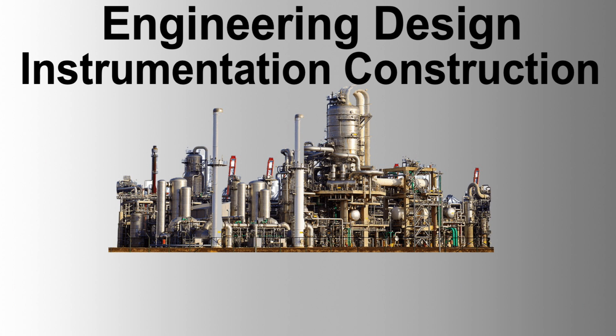Grounding and shielding. Instrument cables with shields shall have their shields grounded at one end only, unless otherwise specified. Grounding shall be done in accordance with the project documentation and best practices to minimize electrical interference. Cable bending and support. Cable bending shall be done in accordance with the manufacturer's recommendations to prevent damage to the cables. Supports shall be installed at regular intervals to prevent sagging and mechanical stress on the cables.